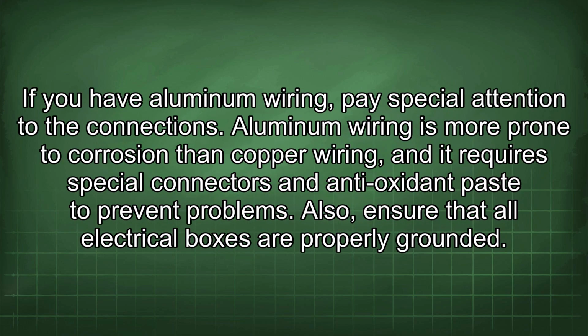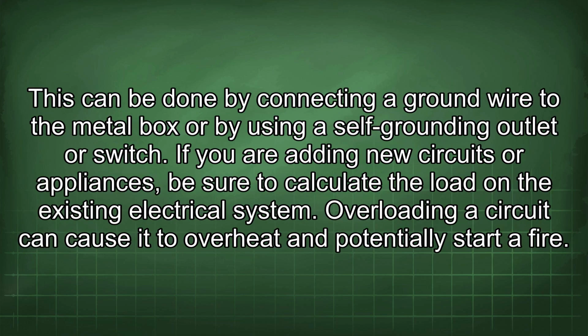If you have aluminum wiring, pay special attention to the connections. Aluminum wiring is more prone to corrosion than copper wiring, and it requires special connectors and antioxidant paste to prevent problems. Also, ensure that all electrical boxes are properly grounded.